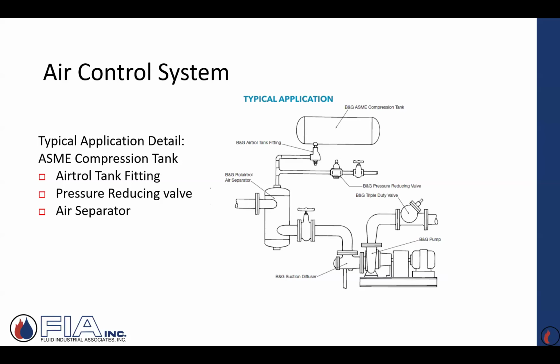Two real quick typical piping or applications, if you will. This is that old system. And when it came out years and years ago, they called it air control. And what you'll notice, one, you get that old style standard tank compression. There are no vents. They did not use automatic vents in an air control system. Because the whole idea is the air and the water, because they were touching each other in this tank, as the system heated, air came out of solution. What I would do is put it through this air separating device, and I'd take any of that air and direct it, control it, send it to that tank.